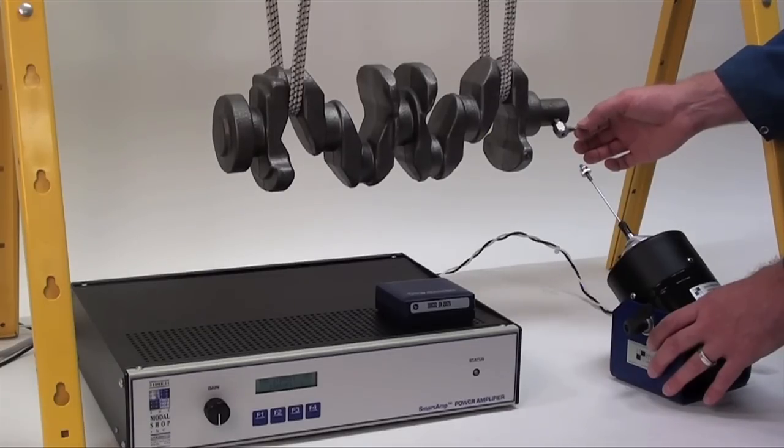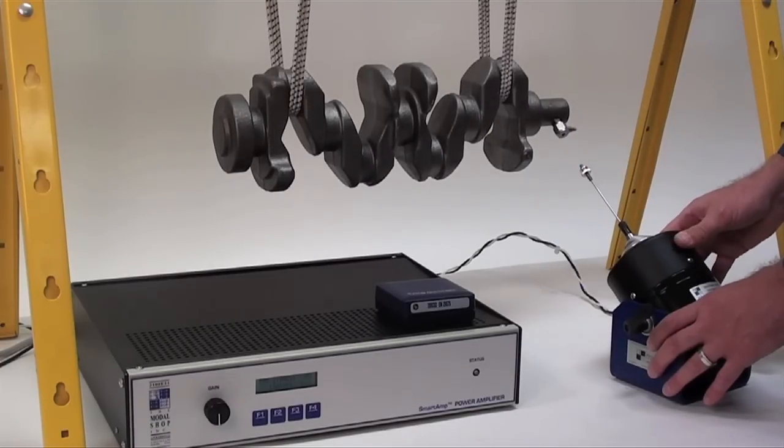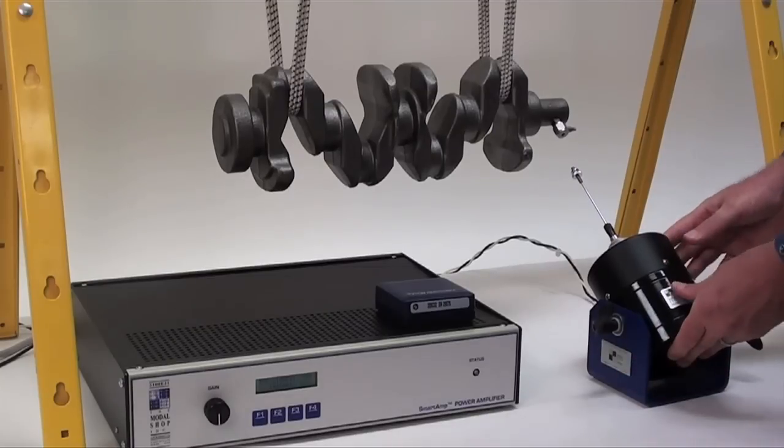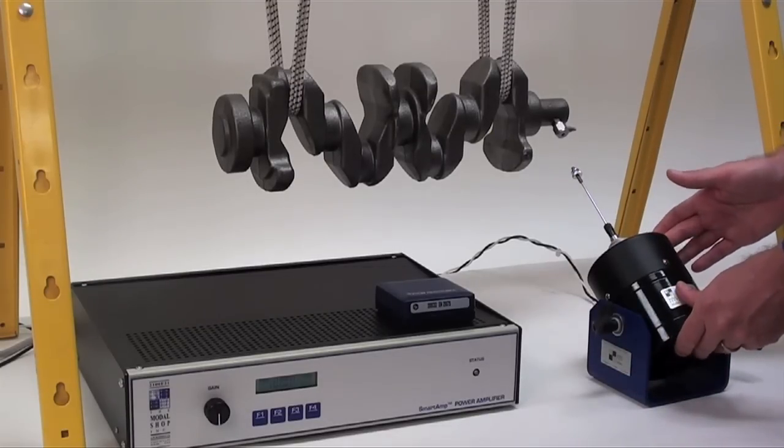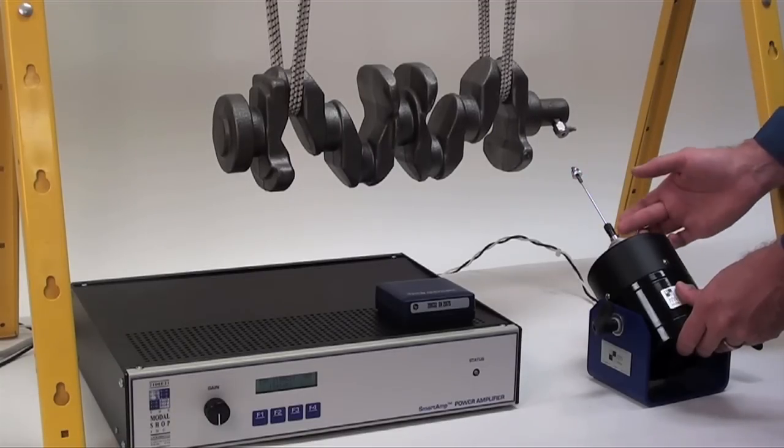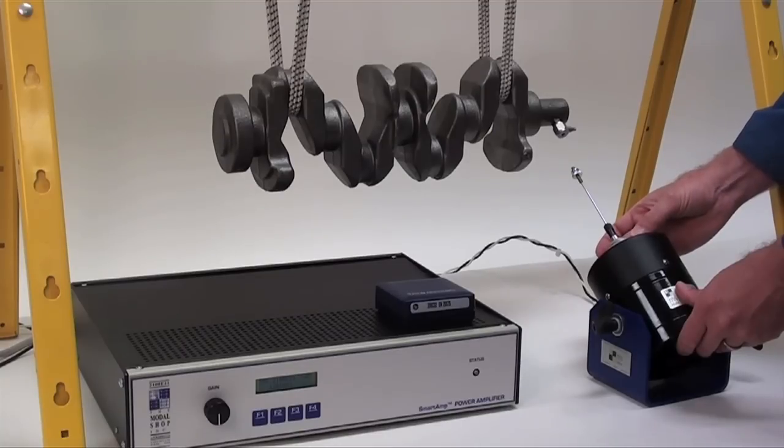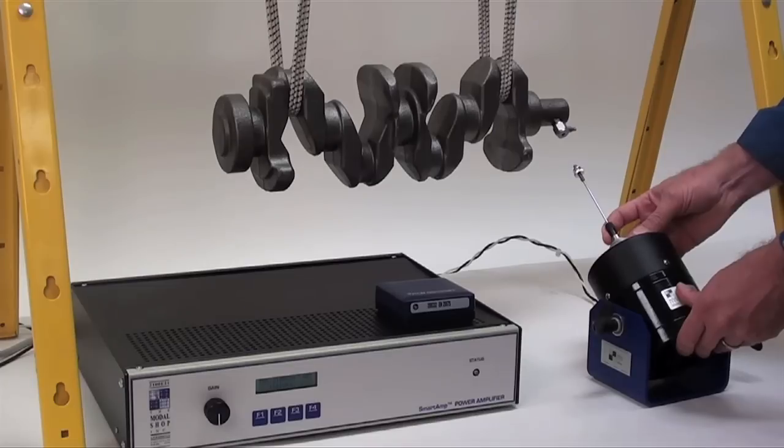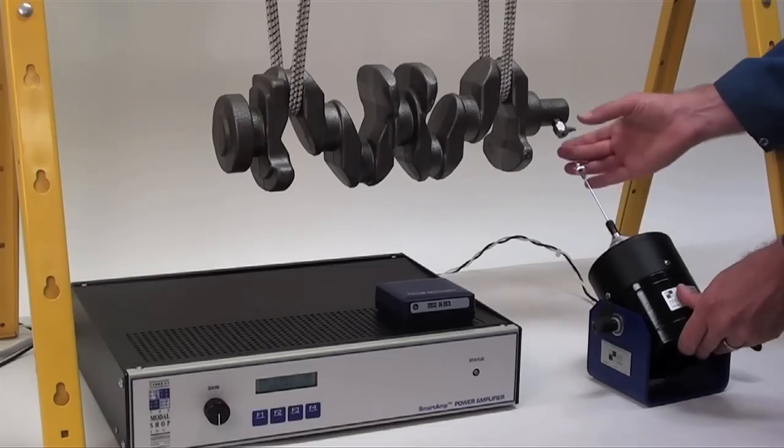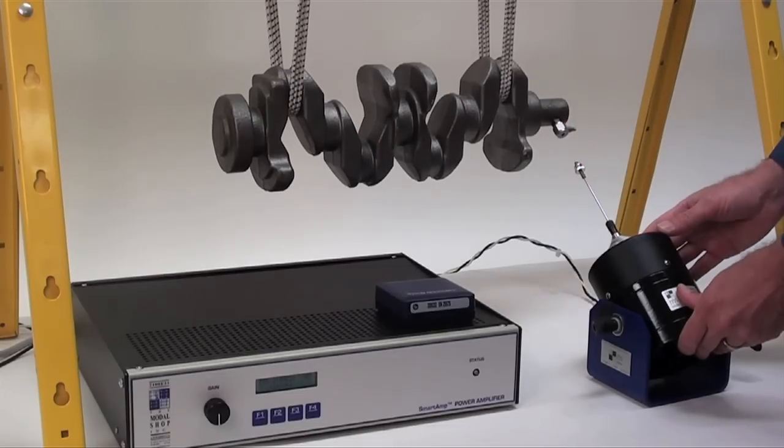And that would add errors to the test. So for that reason, we want to get perfect alignment. For another reason, we want to protect the armature of the shaker. If we have significant side force or moment on the stinger, we may actually damage the support structure inside of the shaker as well. So for those reasons, we want to maintain nearly perfect alignment between the stinger and the load cell.